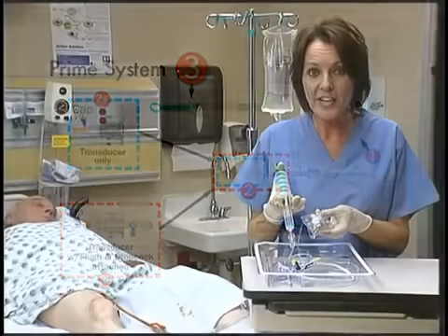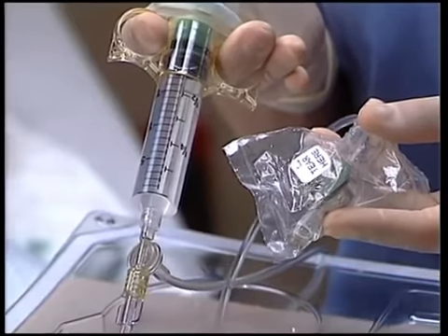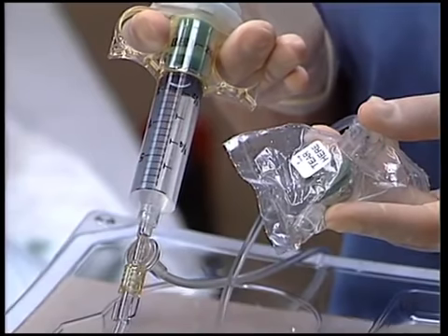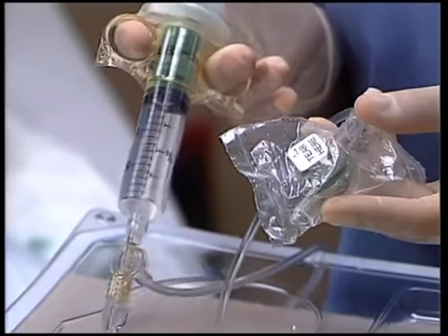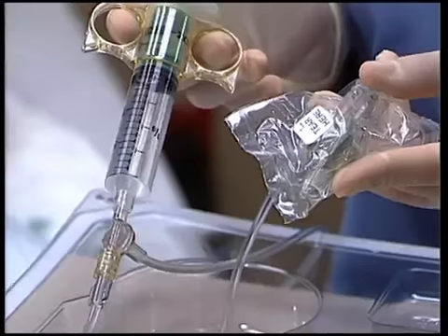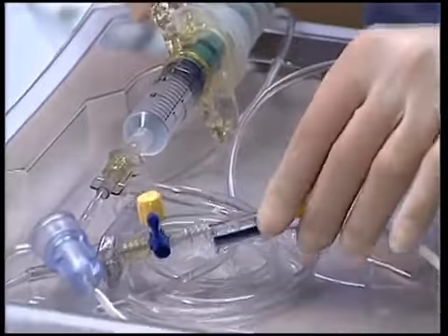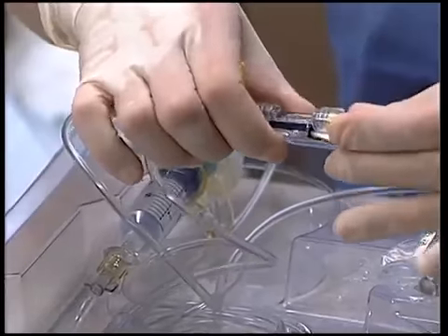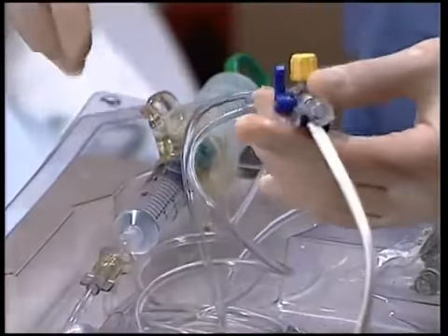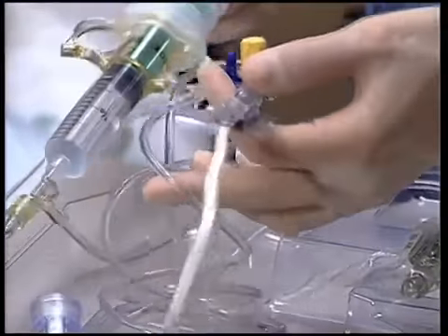Aspirate saline and flush air from the system. Stop injecting saline once it is running out of the tip of the AbViser valve and all the bubbles are cleared from the tubing. Flush the transducer by opening the cap and continuing to inject saline until it runs out of the end of the transducer.